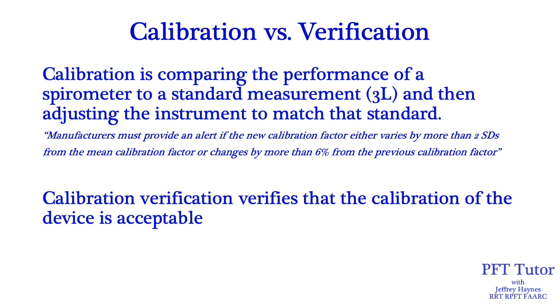Cal or span factors show how much the spirometer reading had to be adjusted to meet the 3-liter target. Ideally, these factors would be close to 1. There are limits on how much the device should be adjusted. For example, the 2019 ATS-ERS spirometry standard states that manufacturers must provide an alert if the new calibration factor varies more than two standard deviations from the mean calibration factor, or changes by more than 6% from the previous calibration factor.